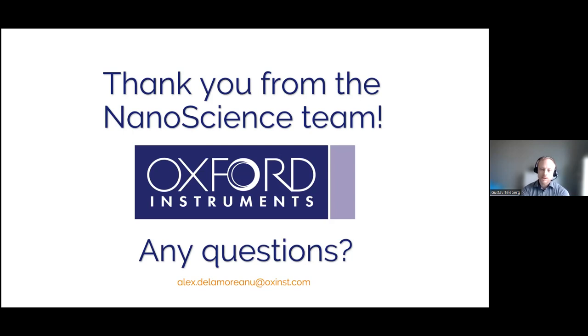So I would say dissipations up to around a milliwatt. If you just want to maintain 100 millikelvin, then you don't really need the 10 millikelvin. Then that's relatively straightforward. We have a sort of off-the-shelf solution for that. If you want to go significantly above that number, within a factor of two it's still within our technical capabilities. If you were to venture above a couple of milliwatts, then you're into territory where I don't think there is a solution based on dilution cooling today. But that's probably where the threshold is.